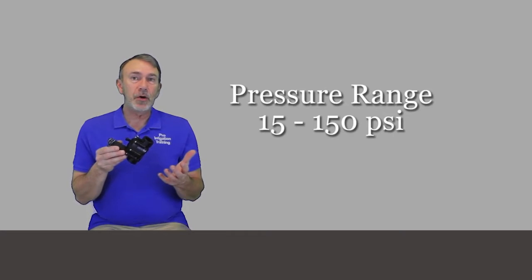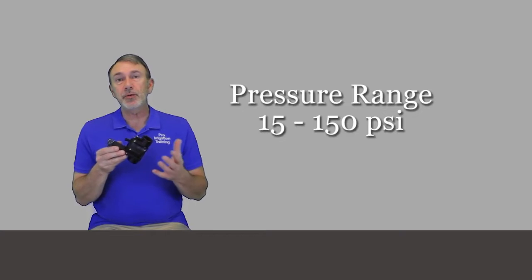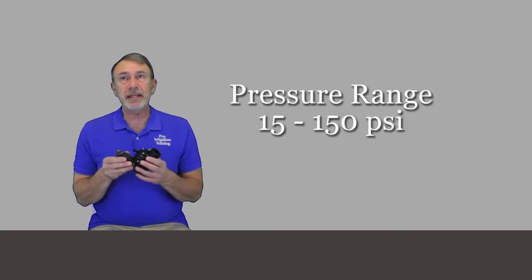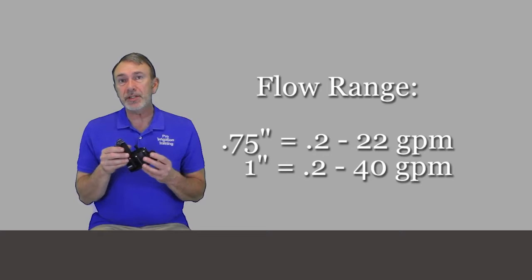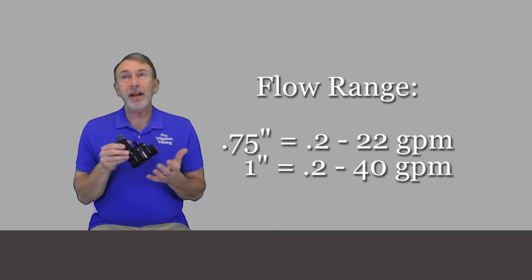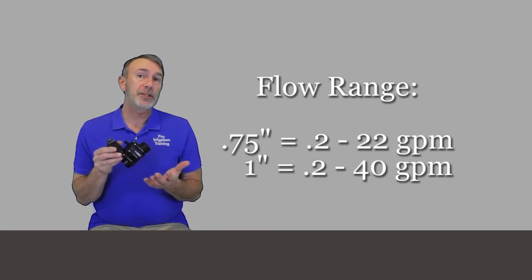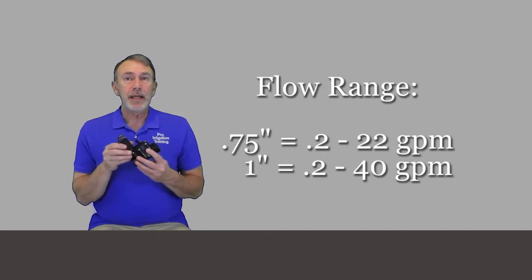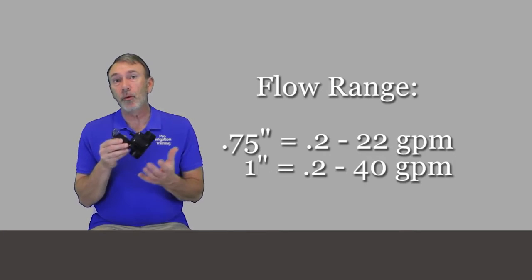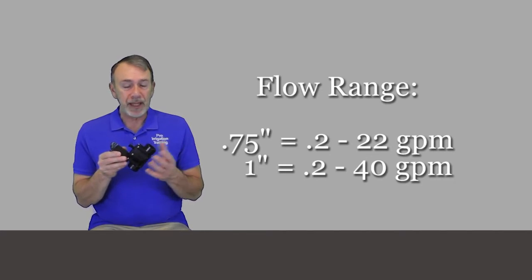Let's talk about some of the specifications for it. The pressure range on it is from 15 to 150 PSI at the inlet. The flow range on it for the three-quarter inch is 0.2 gallons per minute through 22 gallons per minute, and the one inch that I have here is 0.2 through 40 gallons per minute.